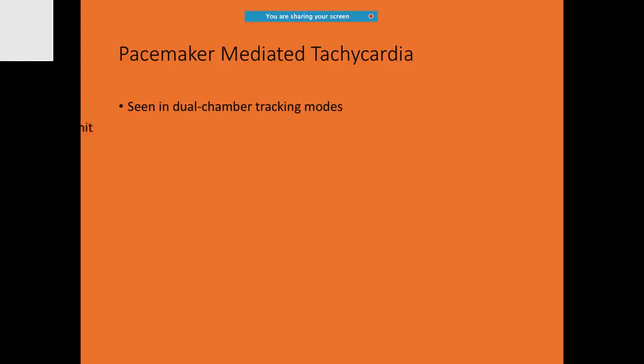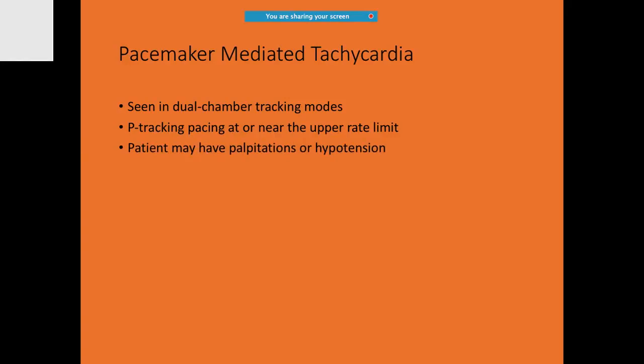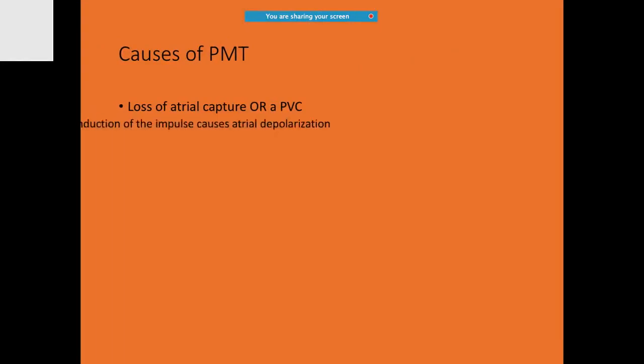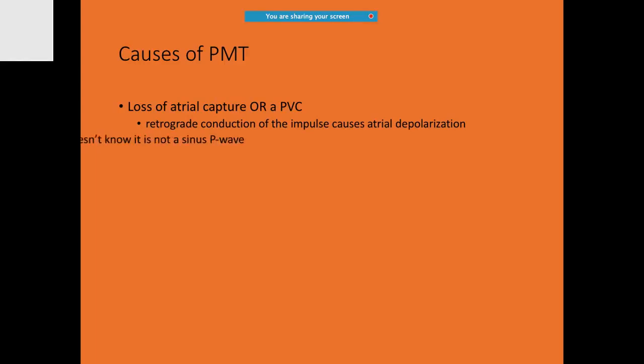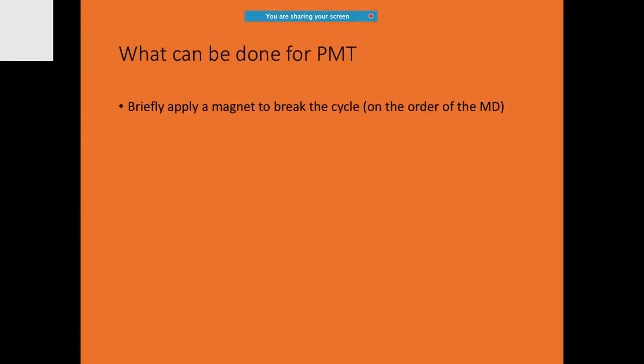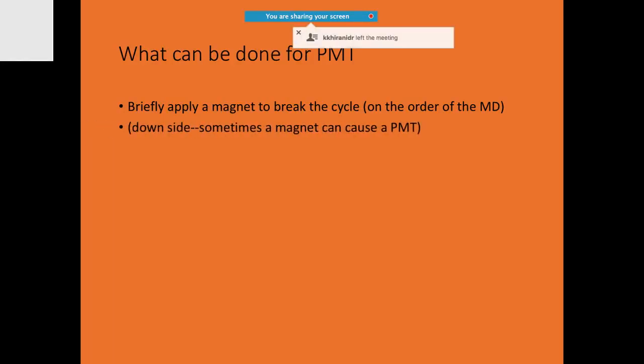A lot of people are already aware of what is called pacemaker-mediated tachycardia. It's mostly seen in dual chamber tracking modes in which the P tracking pacing is at or near the upper rate limit. Patient may have palpitations or even hypotension. It is happening due to the loss of atrial capture or a PVC. The retrograde conduction of the impulse causes atrial depolarization. If there is pacemaker-mediated tachycardia, immediately apply a magnet. But you must not forget, even the magnet itself can cause problems.